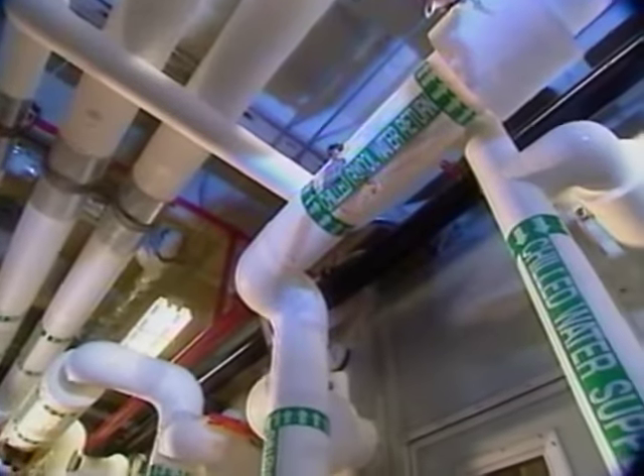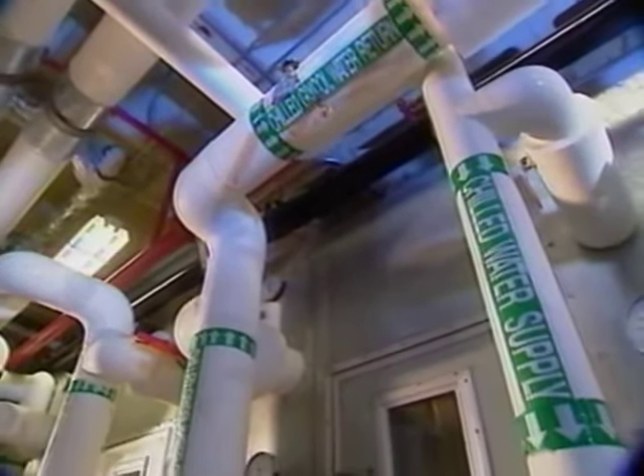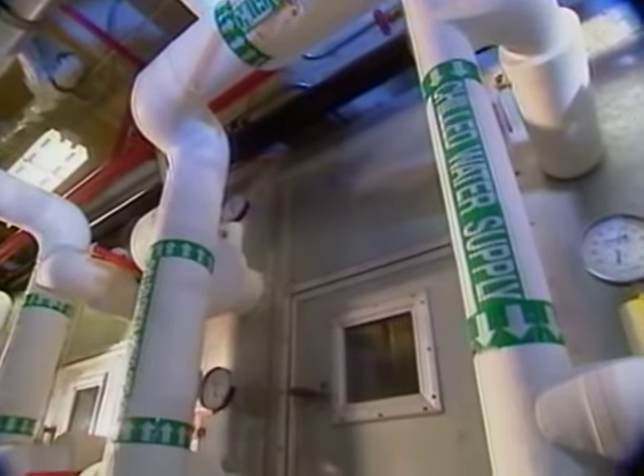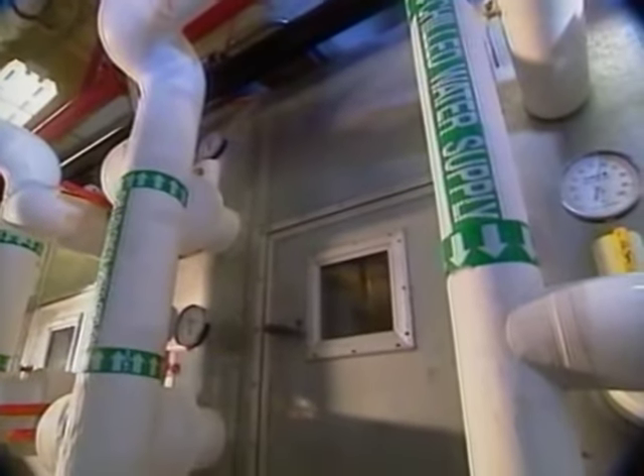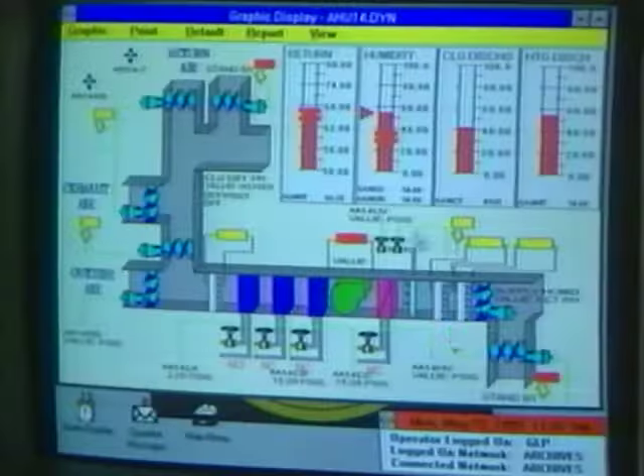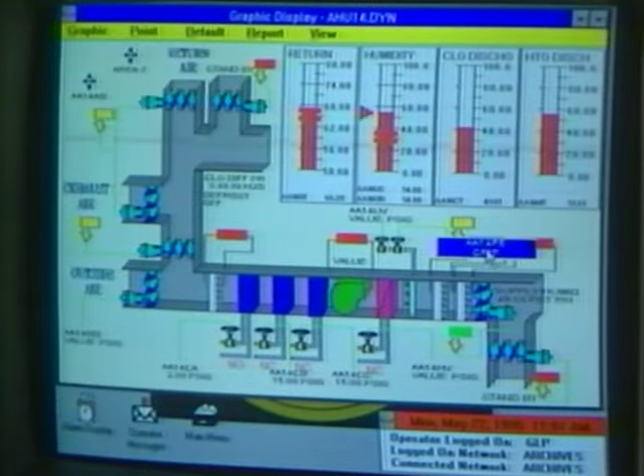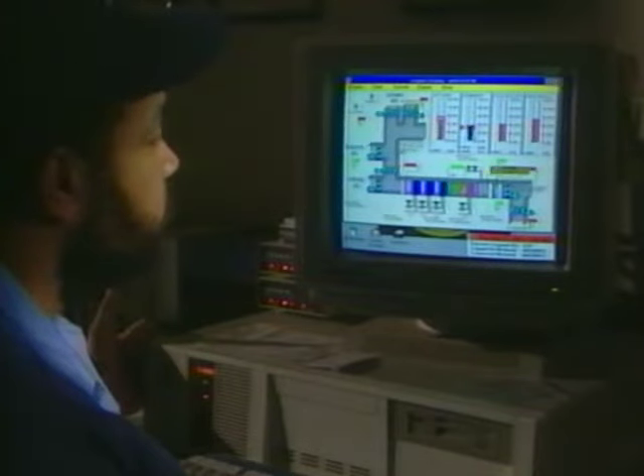In addition, each air handling unit also includes a glycol cooling coil to control relative humidity. Once the air passes through both the chilled water coils and the cooling coils, it is then passed over particulate and gaseous filters to remove the detrimental particulates and gases that produce deleterious effects on the records stored in the stack areas. The temperature and relative humidity of each stack area is monitored continuously and adjustments made by the building automation system located in the central plant.